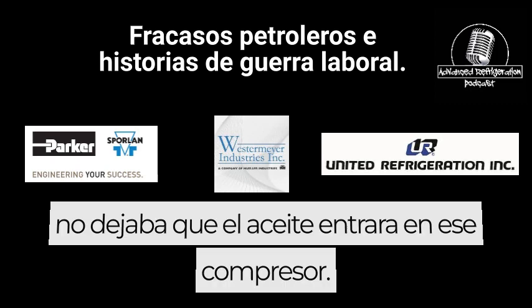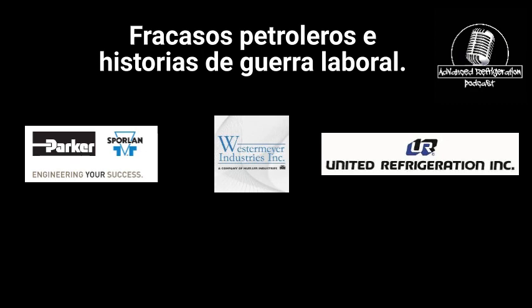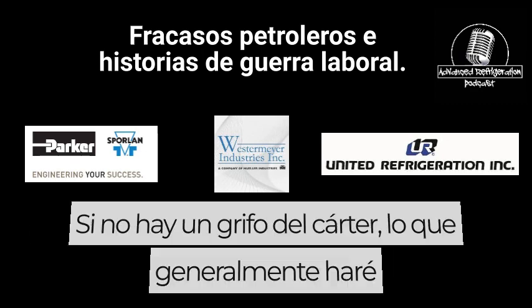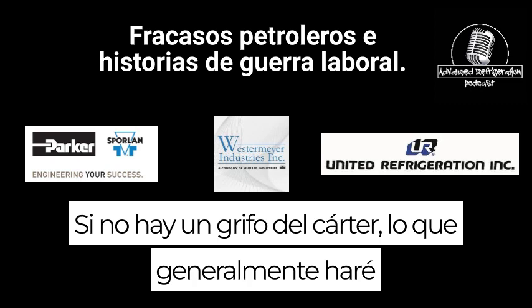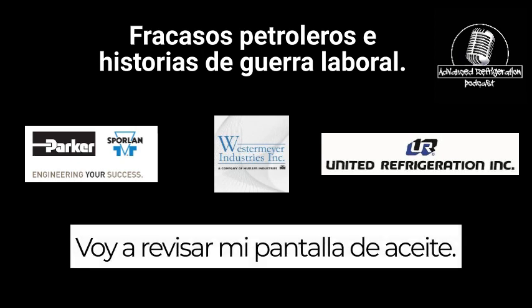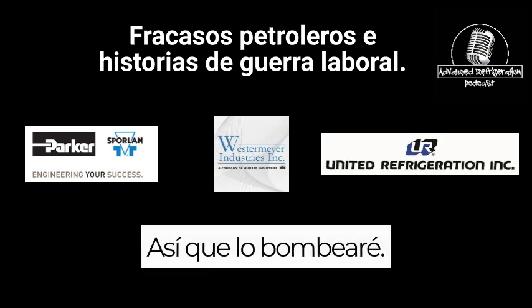And it would not let oil feed into that compressor. So you need to actually see the crankcase pressure. If there's not a crankcase tap, what I will generally do, I'm going to pump the compressor down anyway, and I'm going to check my oil screen. So I'll pump it down.